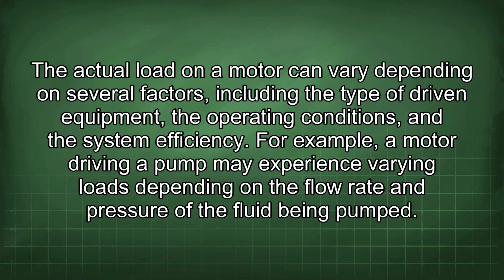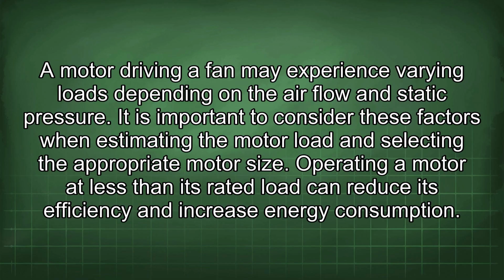The actual load on a motor can vary depending on several factors, including the type of driven equipment, the operating conditions, and the system efficiency. For example, a motor driving a pump may experience varying loads depending on the flow rate and pressure of the fluid being pumped. A motor driving a fan may experience varying loads depending on the airflow and static pressure. It is important to consider these factors when estimating the motor load and selecting the appropriate motor size.